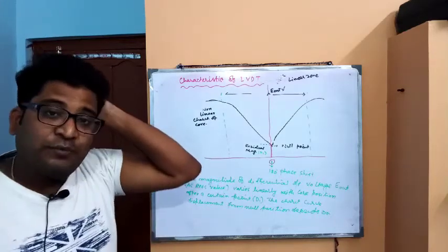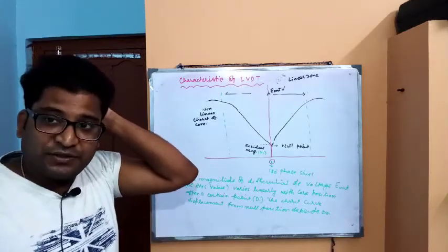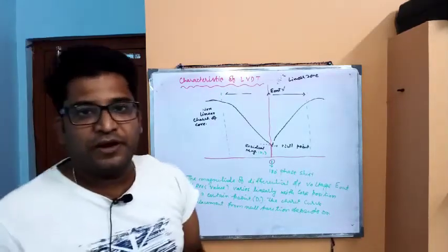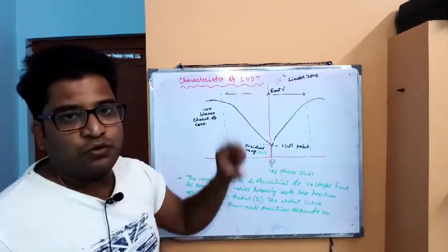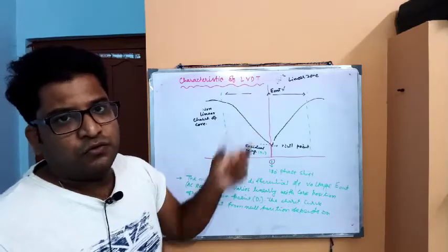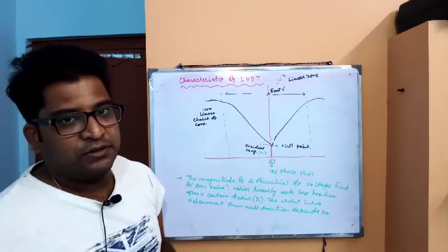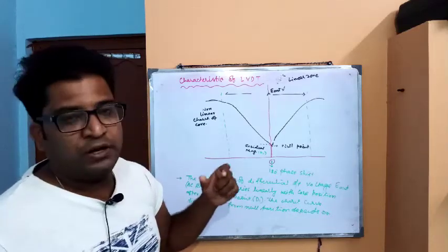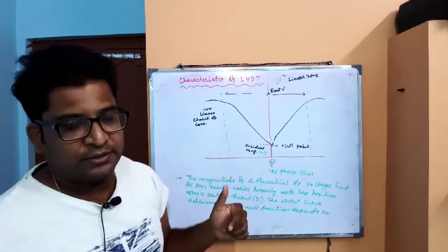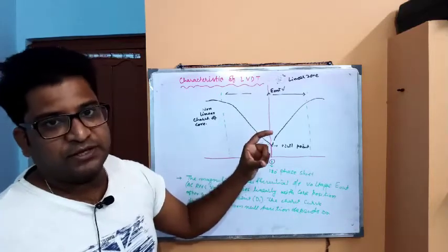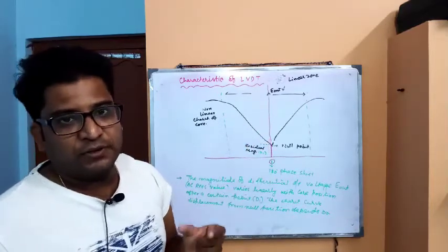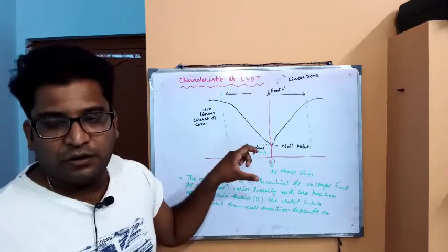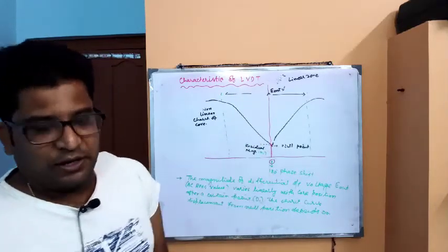We have already discussed that there is a phase shift of 180 degrees when the core moves from upward to downward direction. That means if during the movement in the upward direction the voltage has the positive half cycle, similarly we have the output voltage with the negative half cycle during the downward direction from the null point.